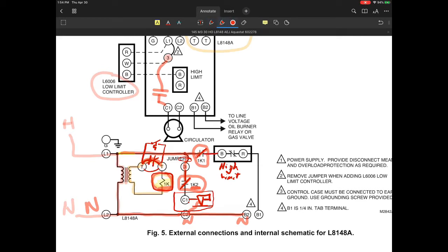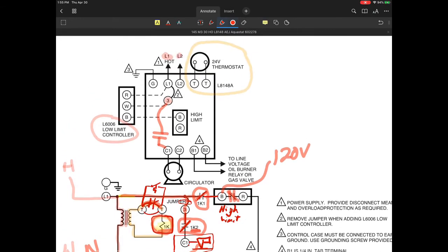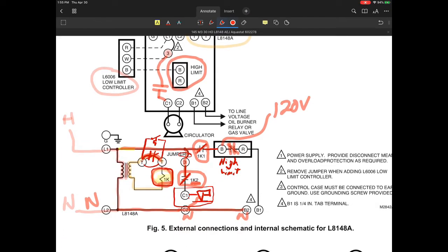So now in this particular case, when there is a demand, the 1K1 sets of contacts, so it's actually the first set of contacts of the 1K relay, will close and provide power, 120 volts, directly to terminal B. So at this point here, I've got 120 volts. If the boiler temperature is below the high limit setting, then what will happen is this will already be closed. That relay, that set of contacts, what they're showing is, that's going to be here between B and R. That set of contacts will close and allow you to continue the path from B to R.